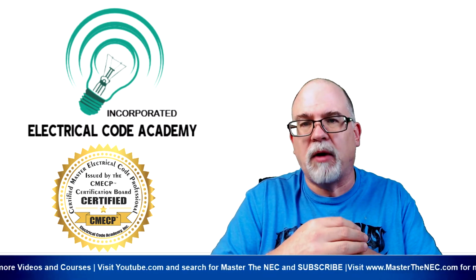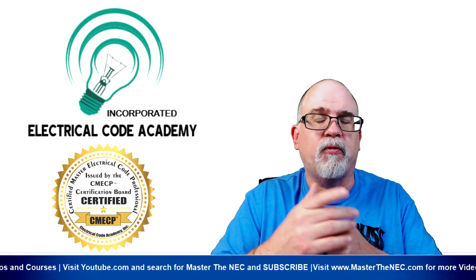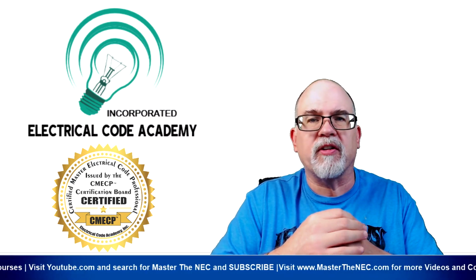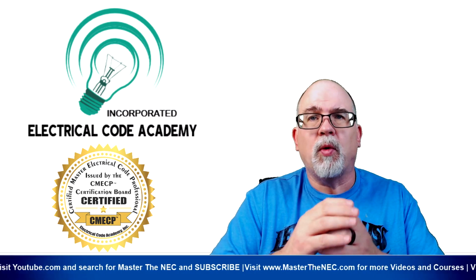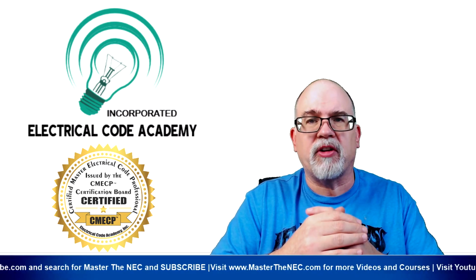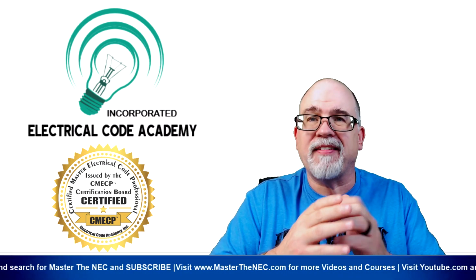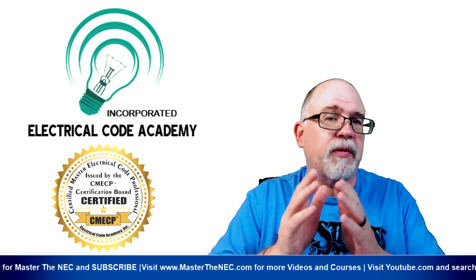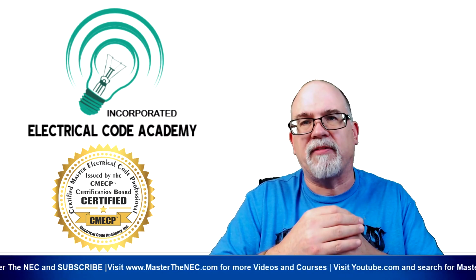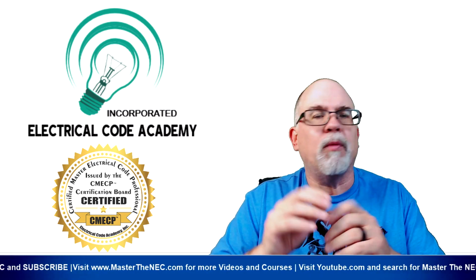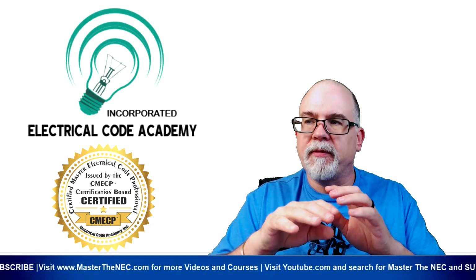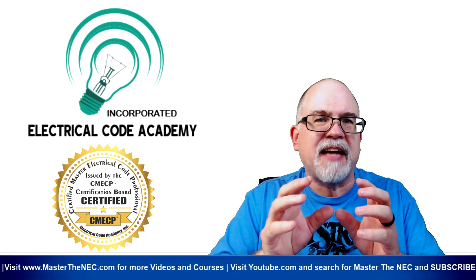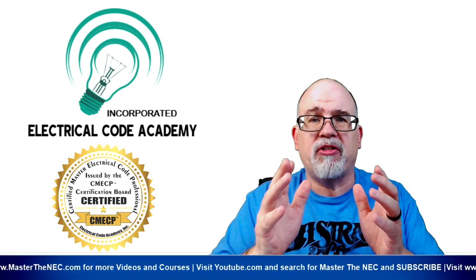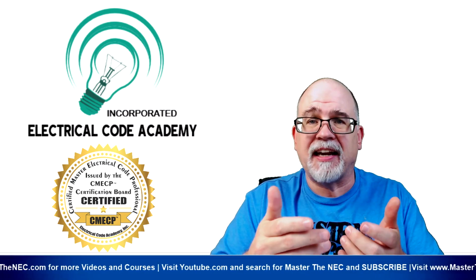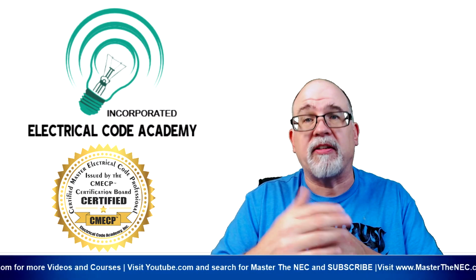Now, we're also going to talk about C1, that's 240.21C1, which is a very obscure rule, whereas the primary overcurrent protection that protects the primary side of the transformer could also serve to protect the conductors on the secondary side of a transformer. It is very unique, and we'll look at it very briefly, but it only applies to two different types of transformers. Any other application, you're going to have primary and secondary protection of those primary conductors and secondary conductors.